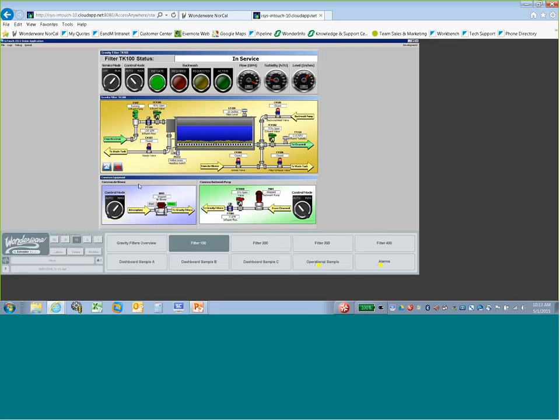So this would be my traditional operator HMI that I use to control my plant. If I want to actually take something out of auto mode and put it into manual, I can control my plant from this, and I can put a plant in manual state and open and close a valve, or turn a motor on or off, or change a set point.